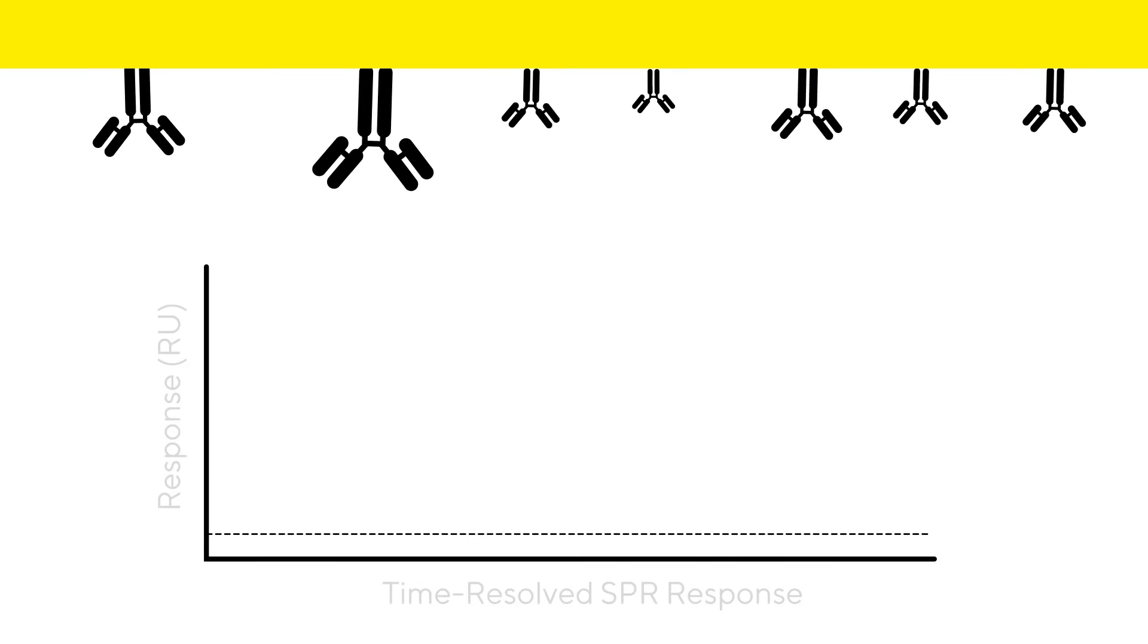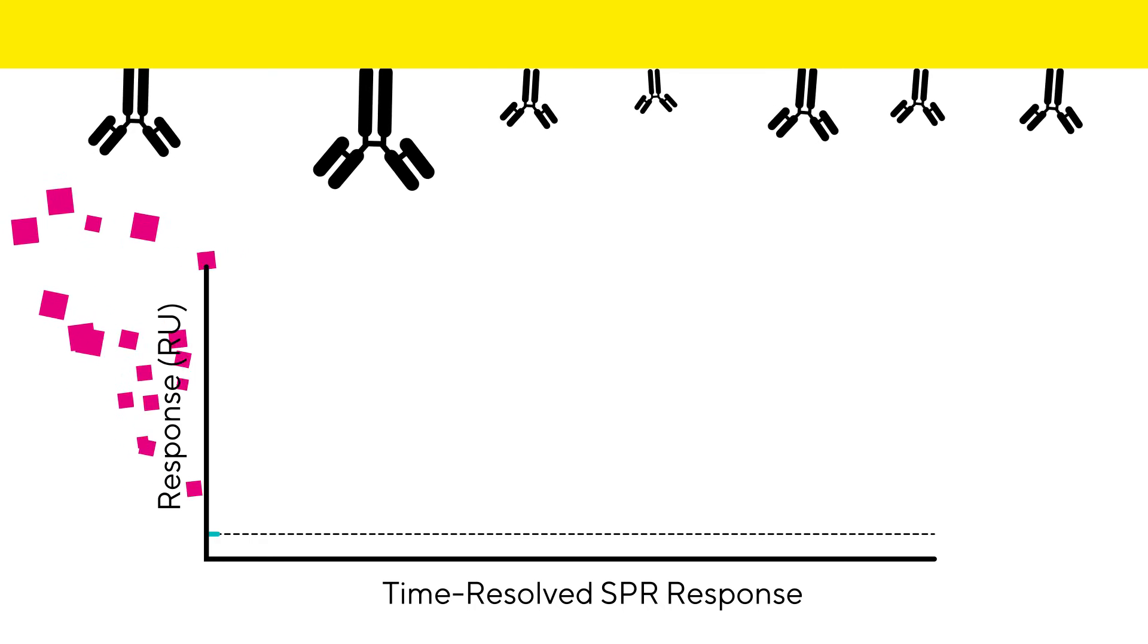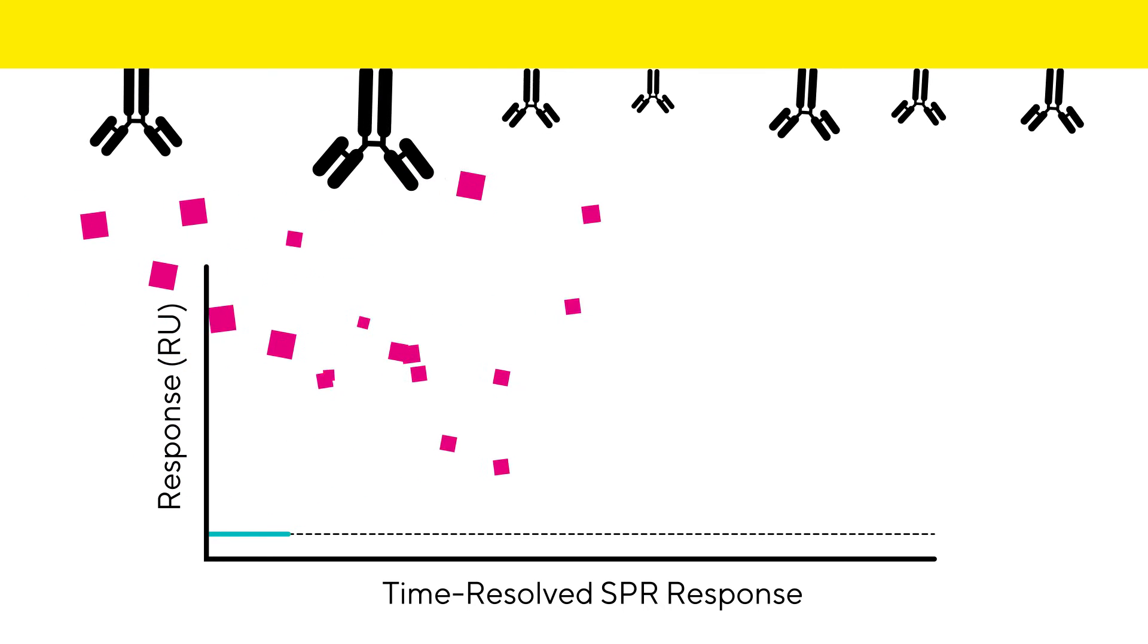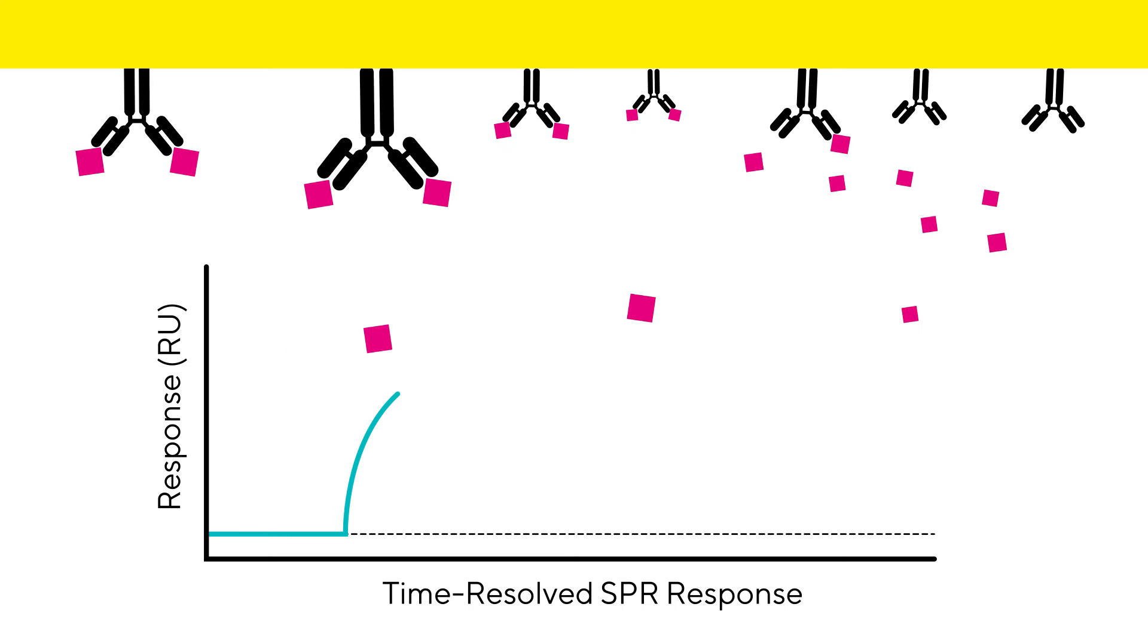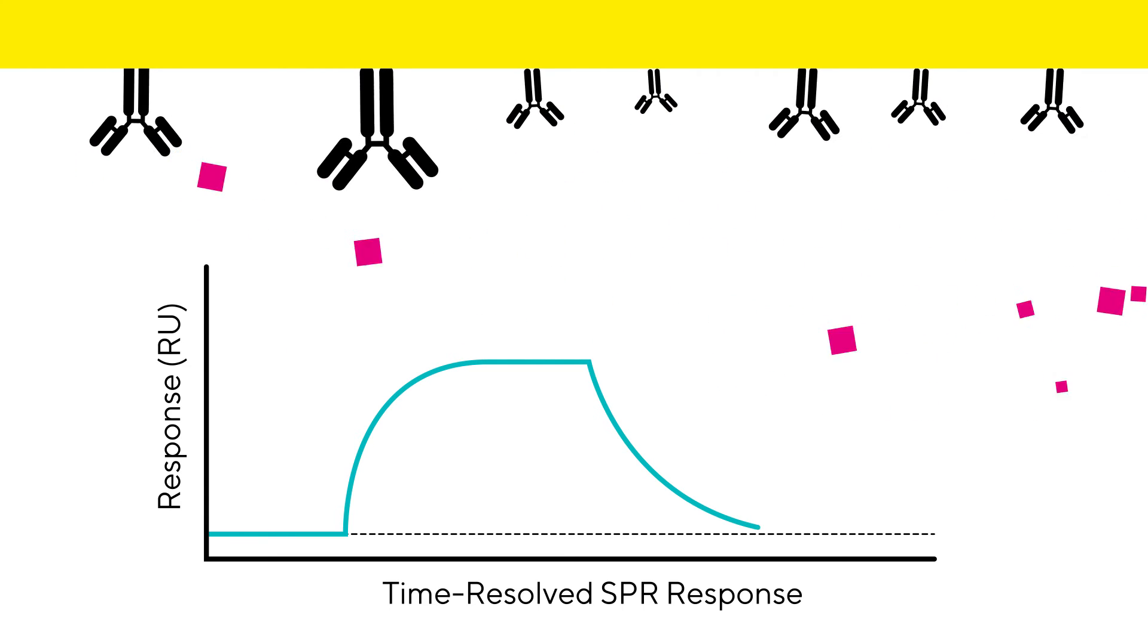When a sample containing an analyte of interest is injected over the sensor chip, any binding of the analyte to immobilized ligands on the chip causes a change in the refractive index at the surface, resulting in a shift in the angle of total reflected light.